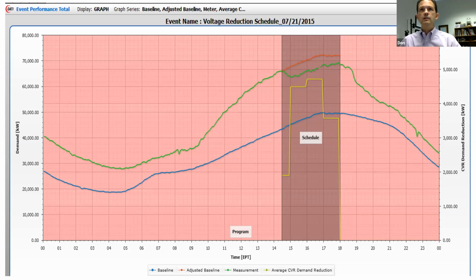In this example, the green line is an actual reading. The darker shaded area is when we were peaking during our coincidental peak with our provider, and the blue line represents a typical day. We activated voltage reduction and lowered demand, as you can see in the dip the green line takes. The red line is what we would have forecasted without going into voltage reduction.